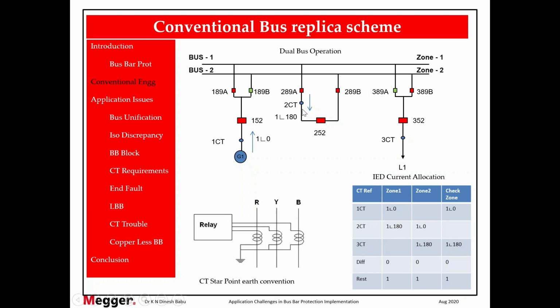So in the conventional system, what we used to do is have two cores and two CTs. Core 1 will be earthed towards bus 1, core 2 will be earthed towards bus 2 to provide this angle change. However, in a numerical relay, this angle change is done mathematically inside. So what we do here is 180 plus 180; 180 will always be added in bus 2.